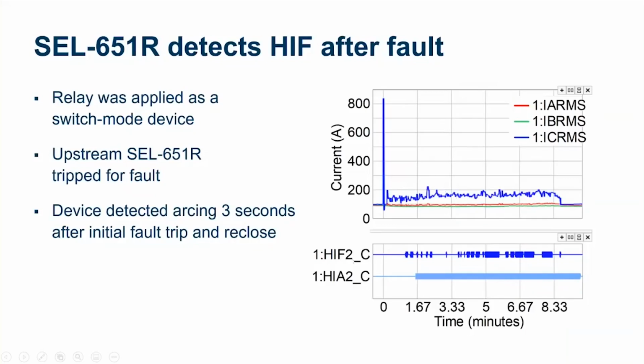So this is my high impedance fault trip on C phase. This is my high impedance fault alarm on C phase. You can see that the alarm came in a minute after the arcing started, but the trip bit was constantly chattering. It didn't assert throughout, but it chattered a little bit. So let's see how these bits asserted, the HIF2 and the HIA2. Again, this is for alarming and this is for fault.